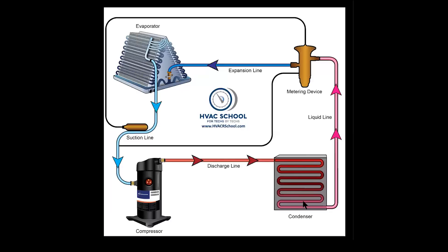That's what happens when the system essentially pumps down — and that's the second analogy. If you've worked in air conditioning, we've all pumped down a system by shutting off the liquid line at the outlet of the condenser. You have systems designed to pump down in both air conditioning and refrigeration. You shut off the liquid line or king valve, the refrigerant pumps down into the receiver or condenser, and then it shuts off on a low pressure switch. It's actually a good thing for the system to pump down because it helps prevent refrigerant migration into the compressor crankcase.